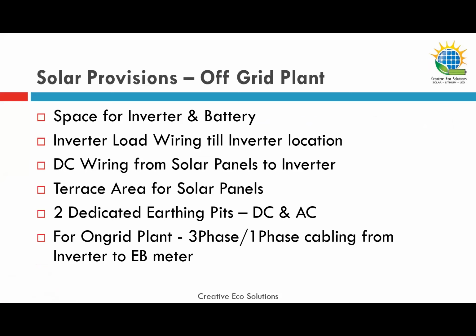When we plan for a solar plant, we have to make some provisions. You have to plan space for your inverter and battery, and this space has to be near the solar panels, since the panels will occupy your terrace area. You can have a staircase room or a lift room, or a space near the lift room, to keep the inverter and battery. If it's a new site, you can plan a small room nearby. For an existing house, you can plan under the staircase at the ground floor, or at the headroom on the terrace level, so the inverter and battery remain visible and you can monitor them.